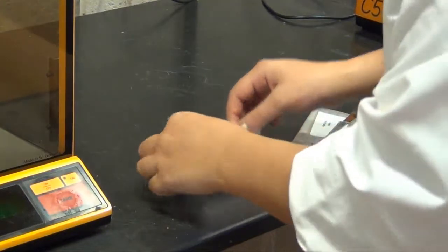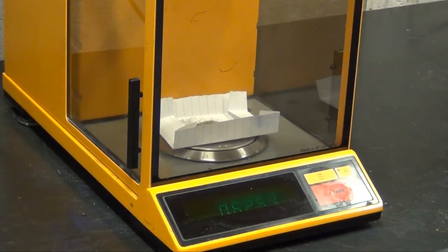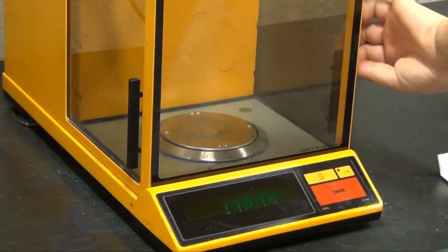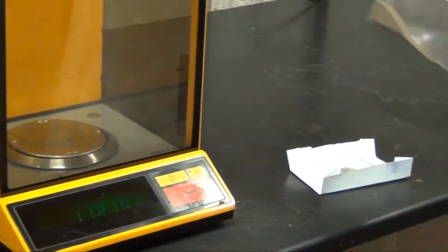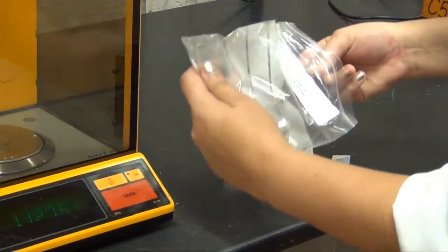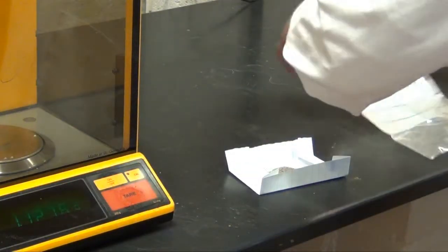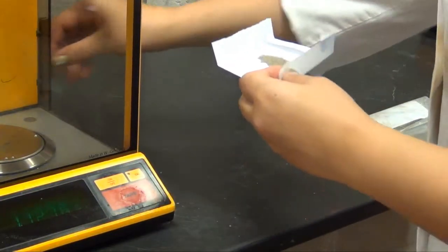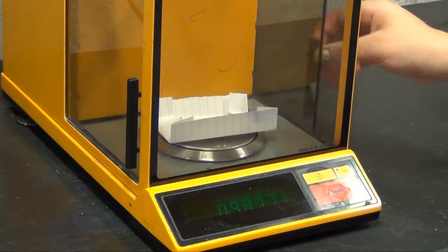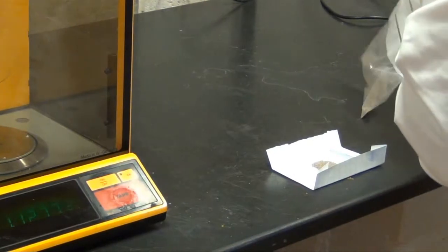None of these adjustments are made over the balance, because that would make further measurements inaccurate. Every time the balance is left, the door is closed. So even for fine tuning of the final required sample weight, the boat must be removed.